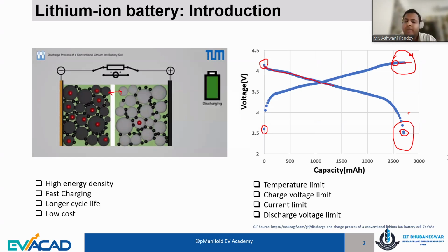From this phenomena, you can appreciate that there is a certain window of lithium ion battery operation, in terms of upper charging cutoff and lower discharging cutoff. There is also a limitation in terms of how much current you can pull out from the system, or how much current you can put in while charging the lithium ion battery - that is called the C rate capability of the battery. In addition, there is also a limit in terms of temperature window for smooth operation. Usually lithium ion batteries do not perform well below 15 degrees Celsius or above 45 to 50 degrees Celsius. So we need to operate the lithium ion battery within those safe and operational limits of voltage, temperature, and current.